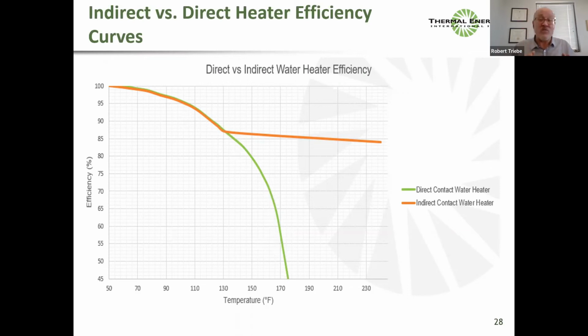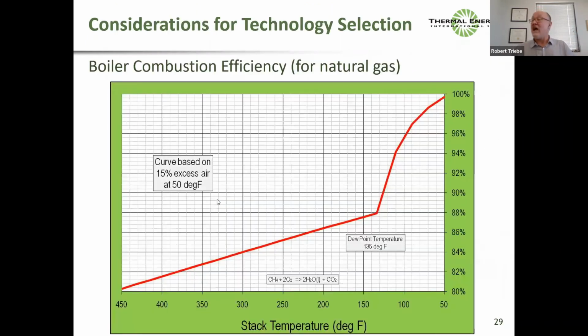So a direct contact water heater can be tremendously cost effective and efficient, and it can also fool people into thinking that they're running efficiently when they're not. So I know that's a deep subject. It might not be fully grabbed, but happy to have discussions, answer questions. And here I'm going to give a little example about the integration as well. Here's a heat recovery curve. Here's 15% excess air, 50 degrees Fahrenheit, exhaust temperature versus efficiency. So that's the normal curve.